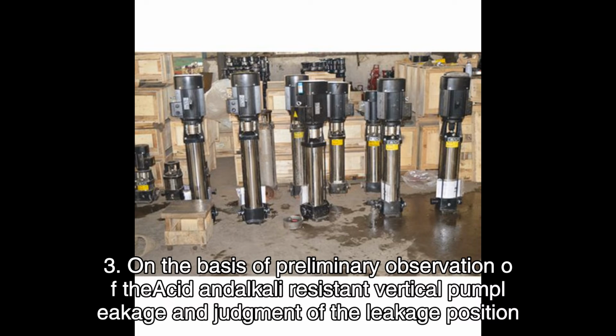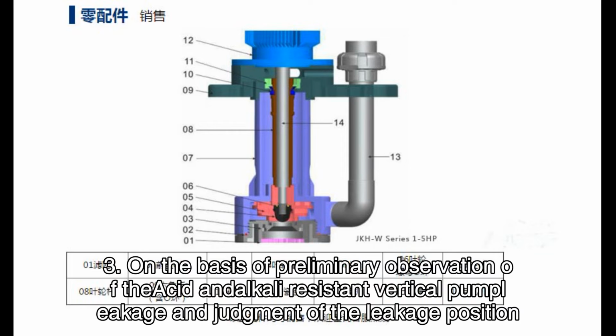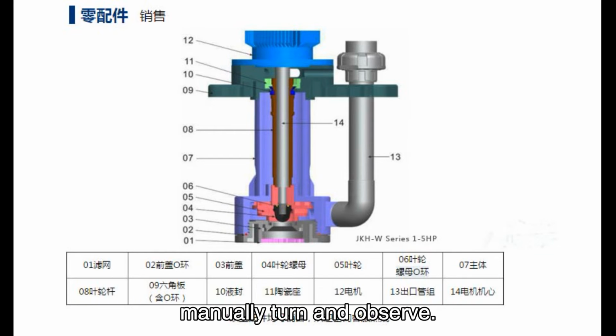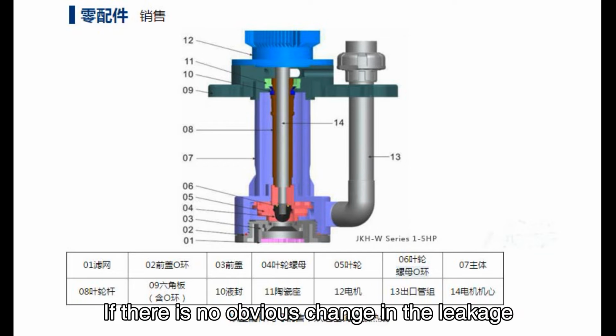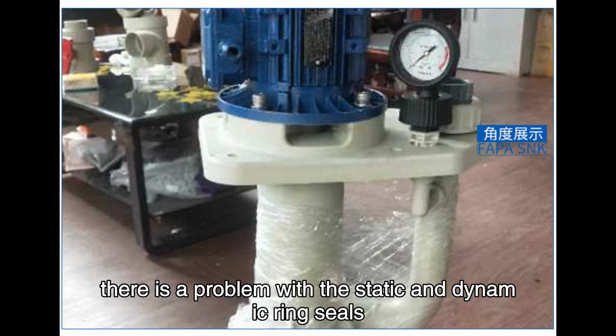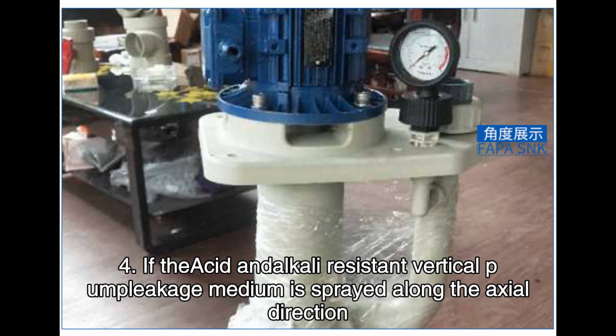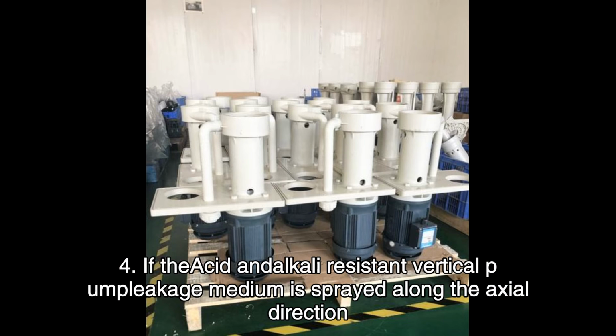3. On the basis of preliminary observation of acid and alkali-resistant vertical pump leakage and judgment of the leakage position, manually turn and observe. If there is no obvious change in the leakage, there is a problem with the static and dynamic ring seals.